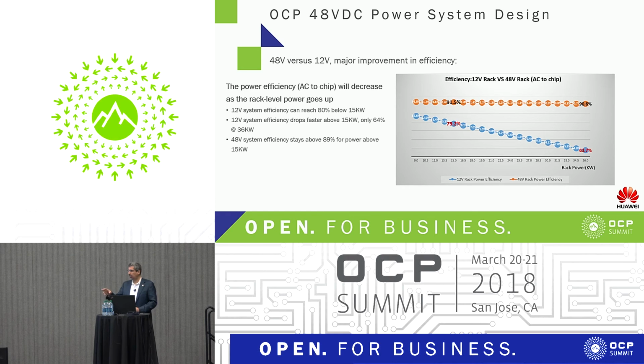That's not exactly right, because if you go to the NEC ratings and capacity ratings for cables, they also have temperature factors involved. So you end up roughly 9 or 10 times difference in cable size, but that's substantial. So I want to point out here, really 48 volts is always more efficient.